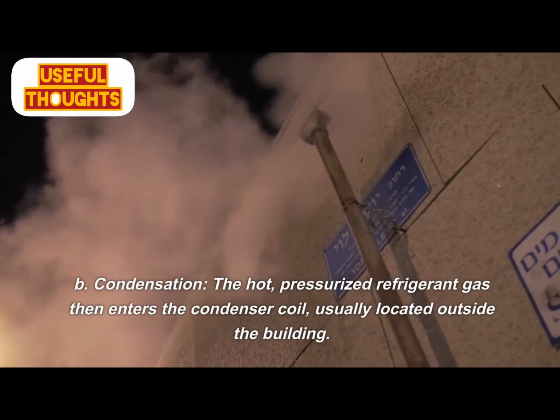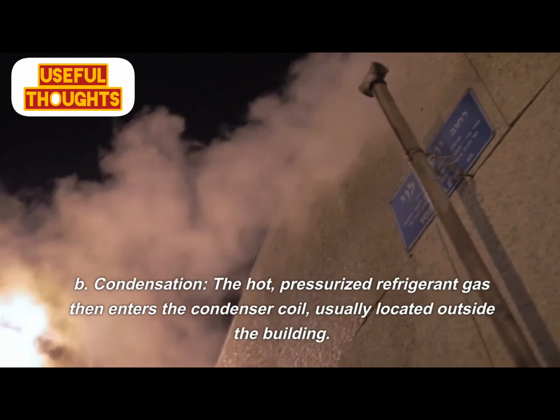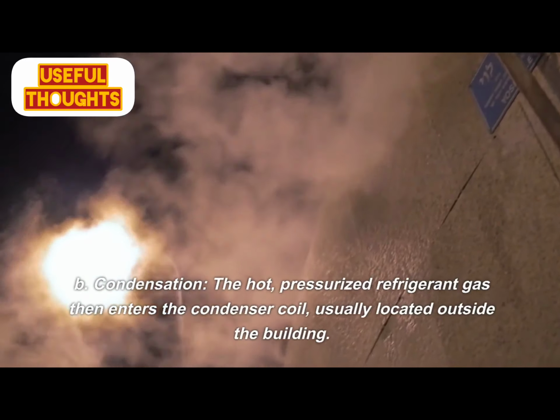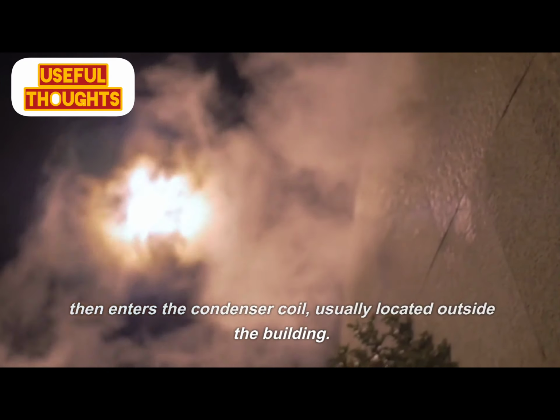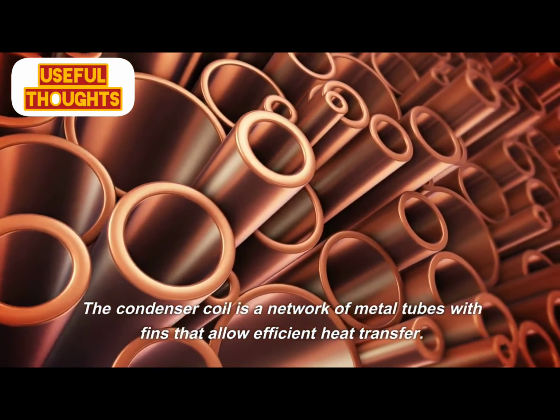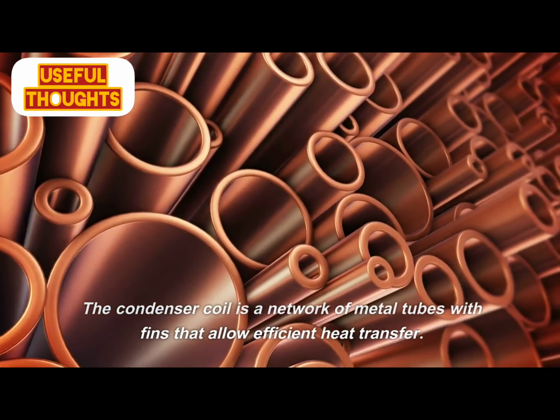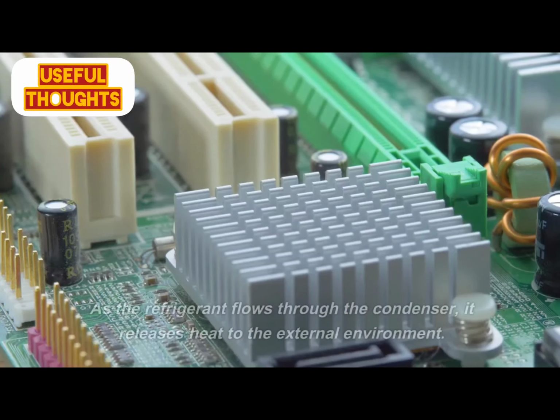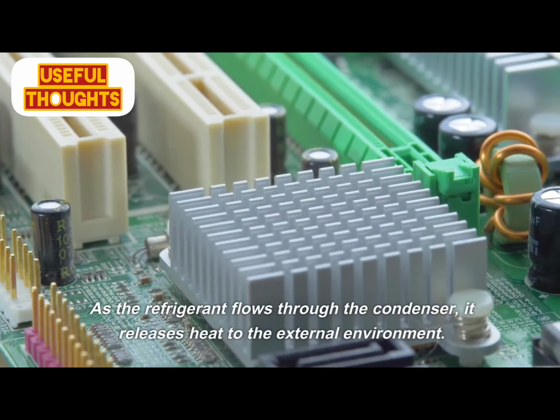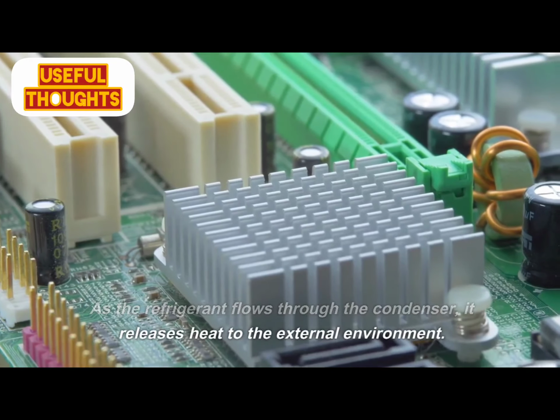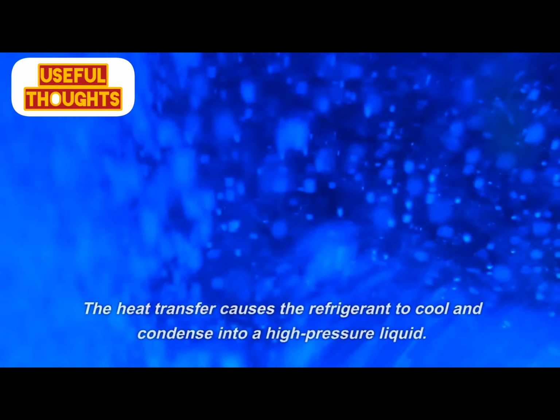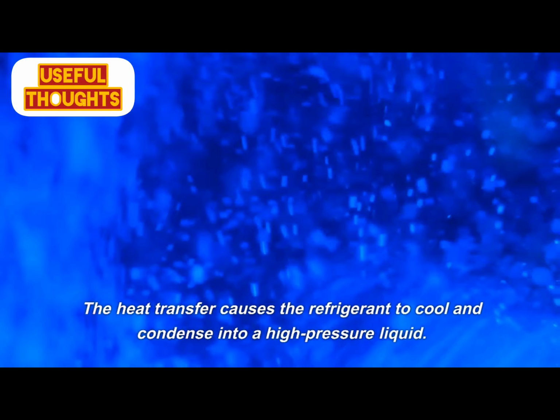B. Condensation. The hot, pressurized refrigerant gas then enters the condenser coil, usually located outside the building. The condenser coil is a network of metal tubes with fins that allow efficient heat transfer. As the refrigerant flows through the condenser, it releases heat to the external environment. The heat transfer causes the refrigerant to cool and condense into a high-pressure liquid.